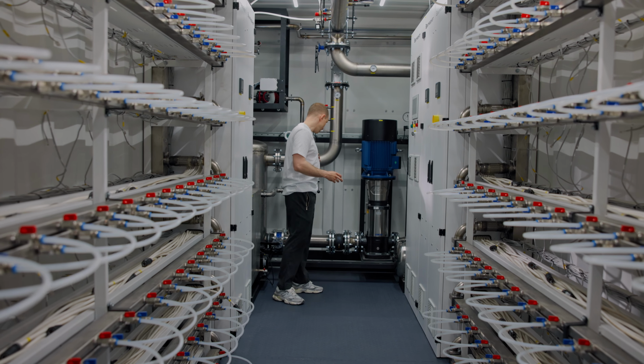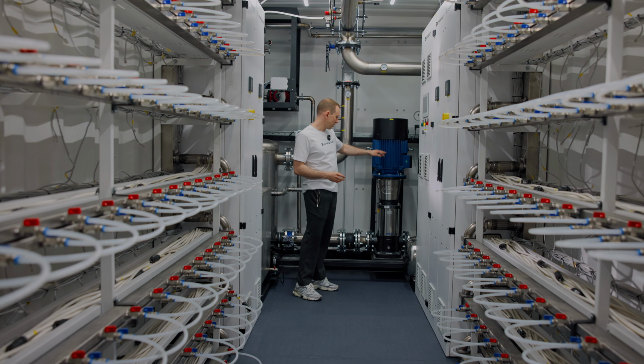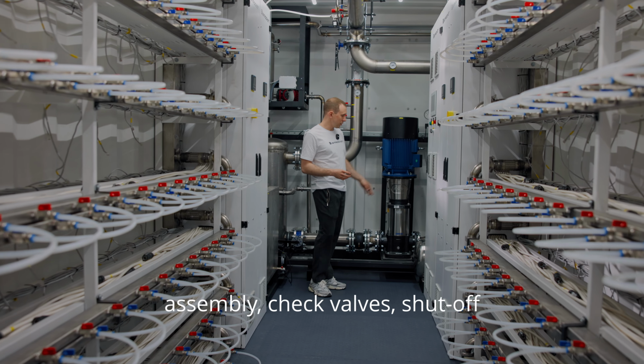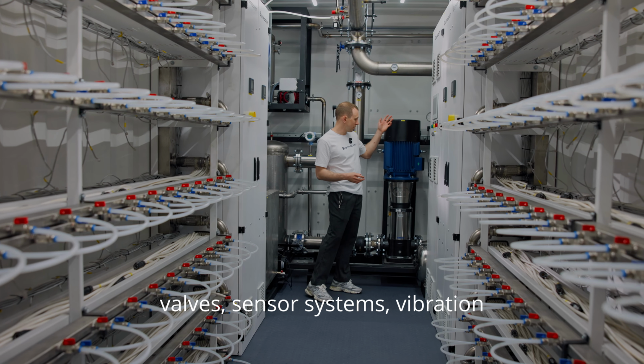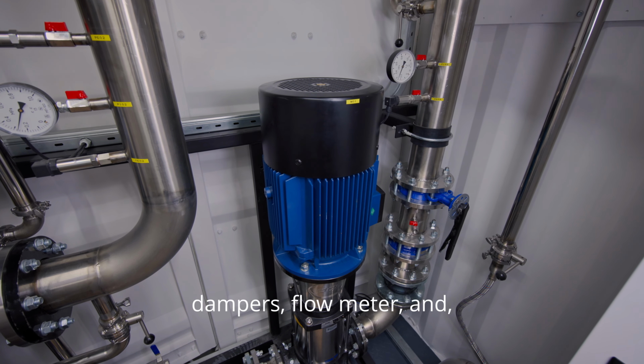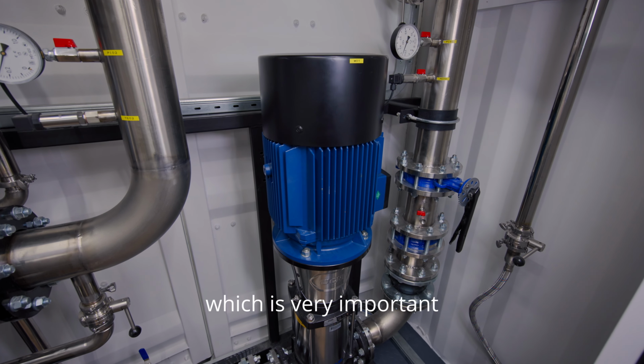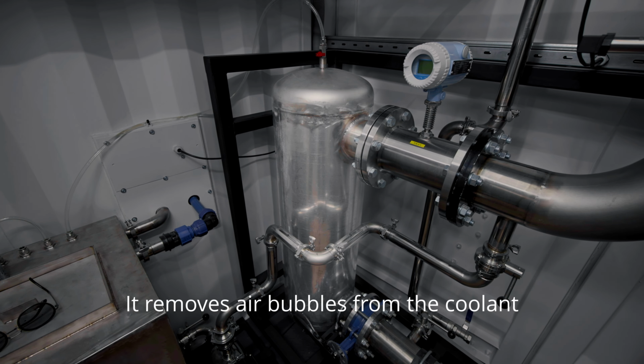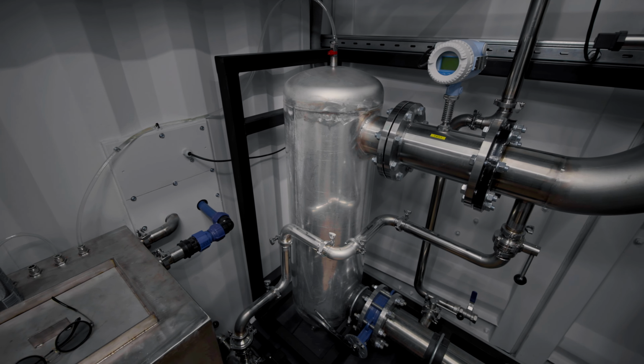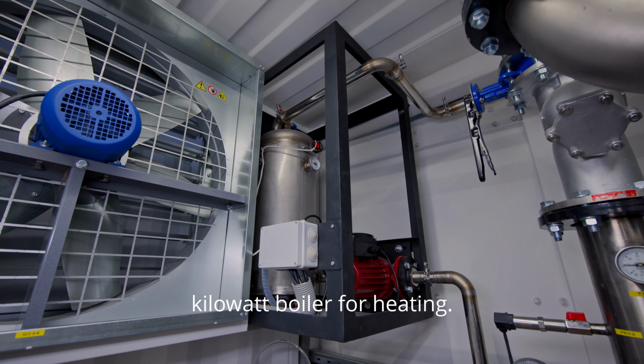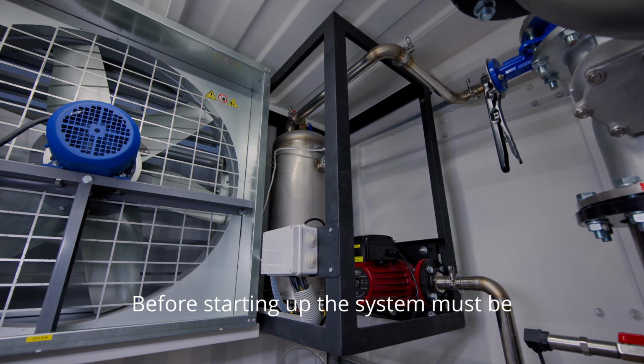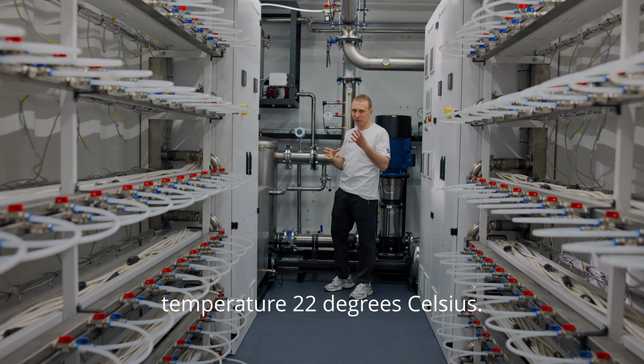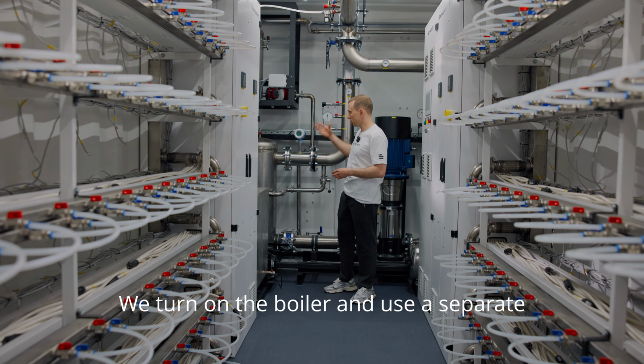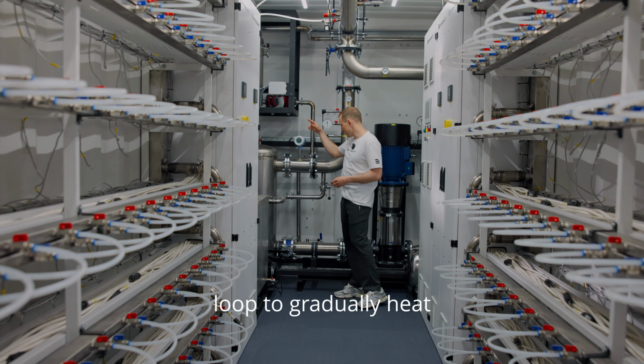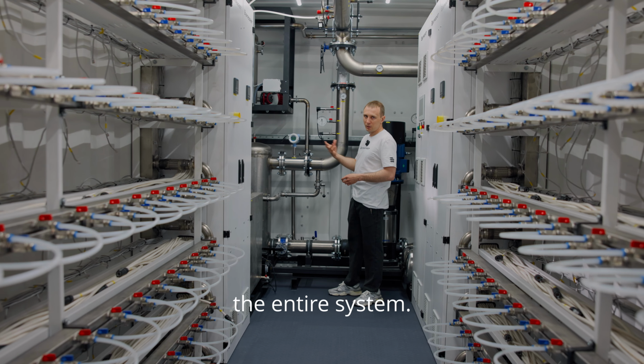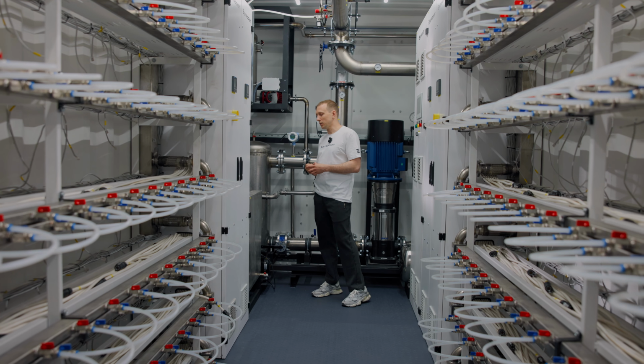The pump unit. The pump unit includes the main pump, piping and valve assembly, check valves, shutoff valves, sensor systems, vibration dampers, flow meter, and, which is very important, the deaerator. It removes air bubbles from the coolant and we release them. Next, we have a 60 kilowatt boiler for heating. Before starting up, the system must be heated to the startup temperature, 22 degrees Celsius. We turn on the boiler and use a separate pump on a dedicated loop to gradually heat the entire system. Then we can start the miners.